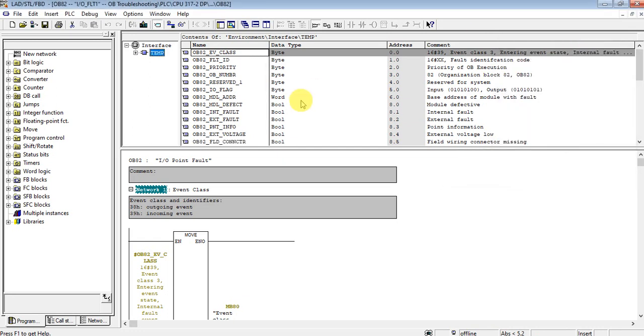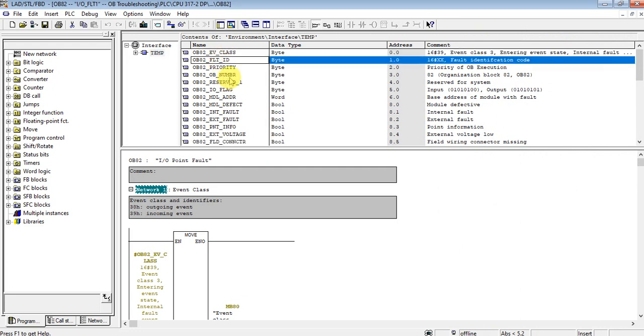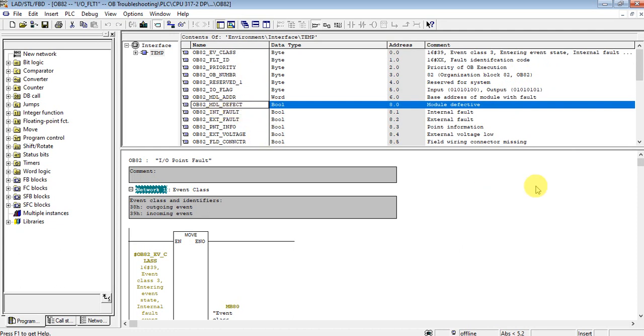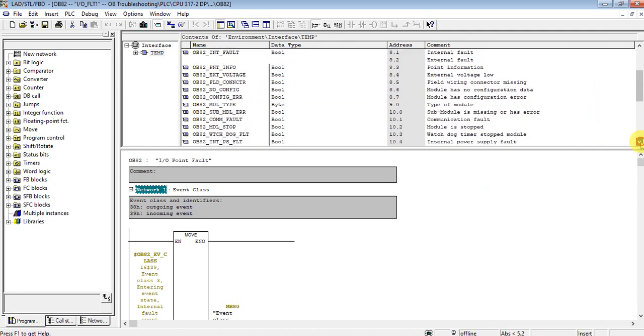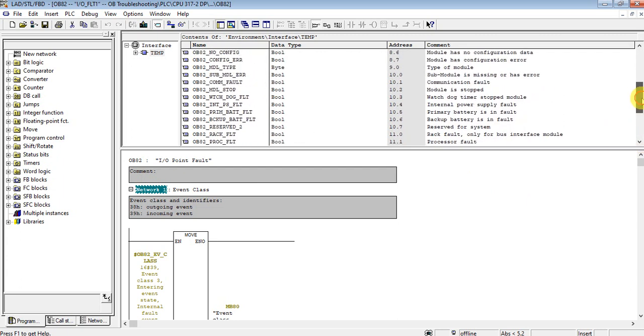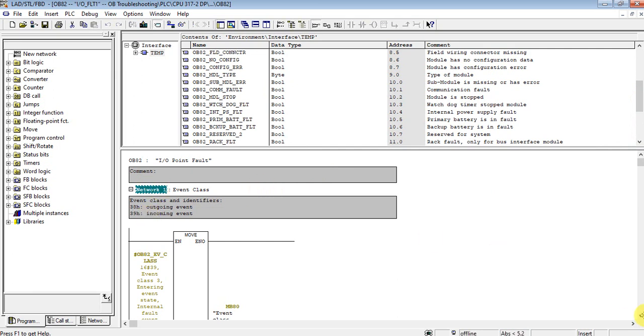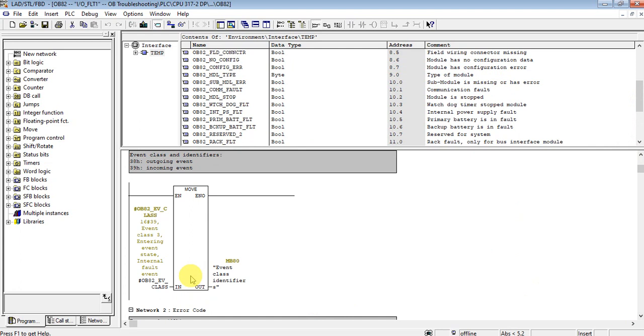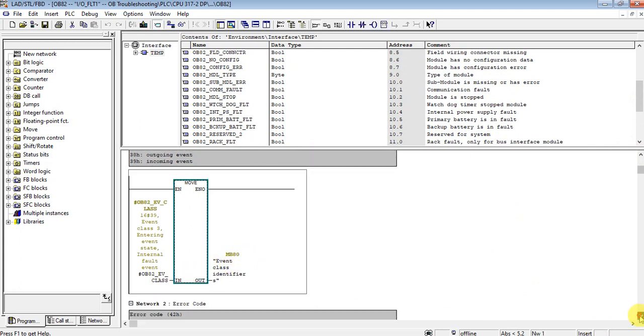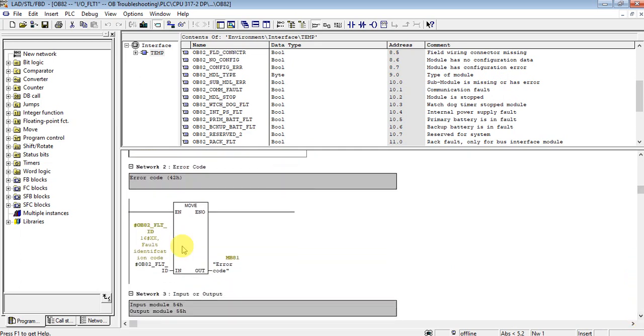Here are the default variables for OB82. There is the event class, the fault ID, and this one is the module address. OB82 has several useful default variables. I have used some of these variables to get information — for example, here is the event class, which I have moved to memory byte 80.